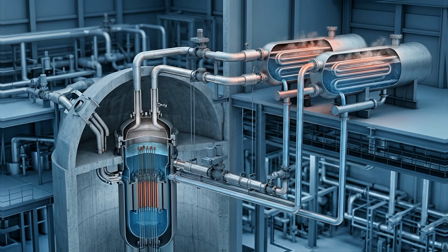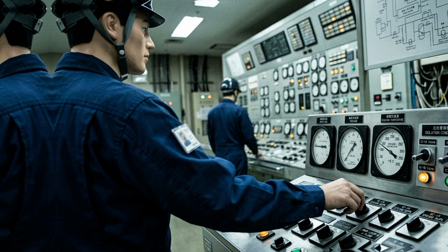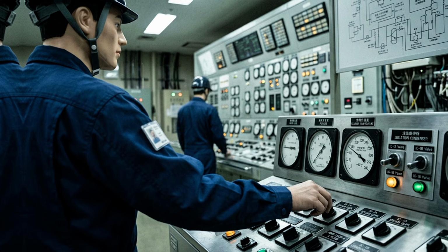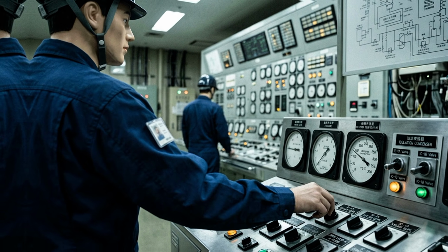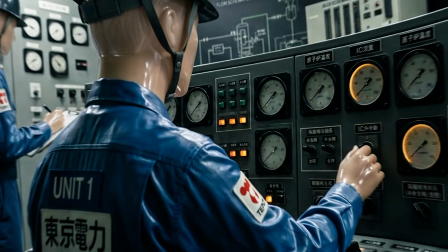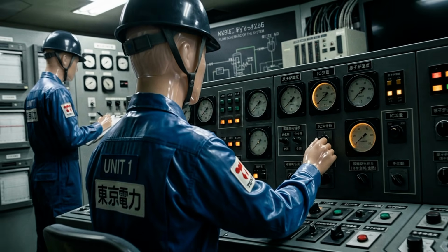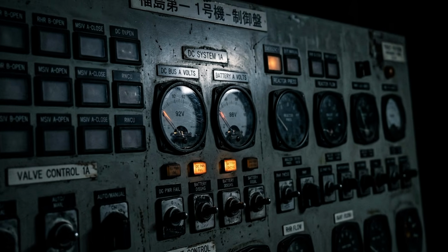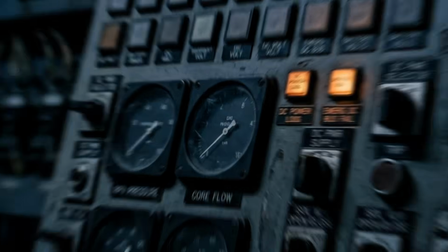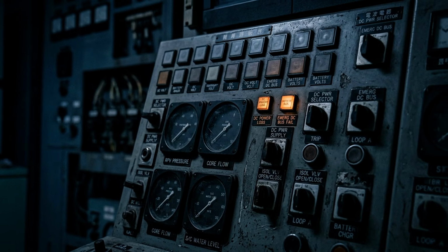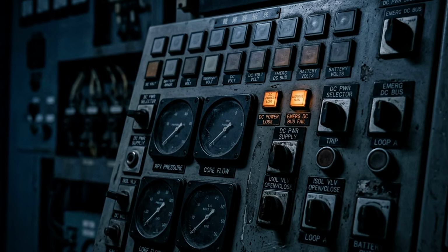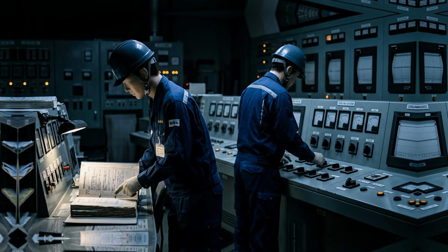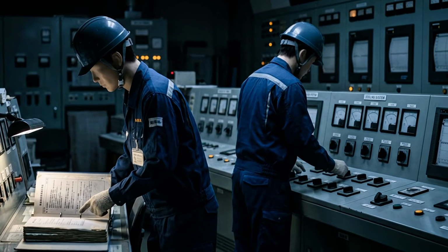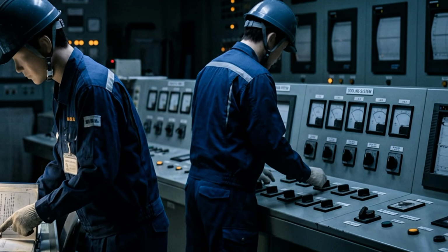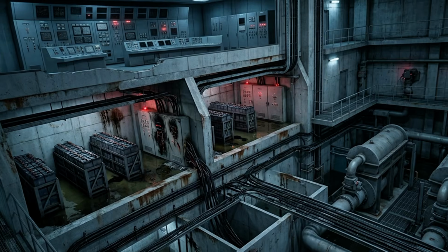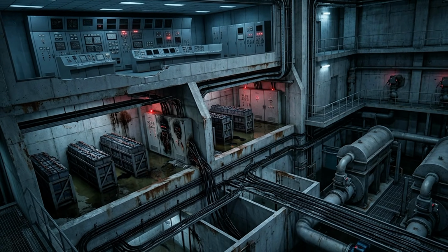After the earthquake, the system started automatically. Operators then stopped and restarted it because the reactor was cooling too quickly. Procedures required them to control the cooldown rate to avoid excessive thermal stress. Just before the tsunami, the isolation condenser had stopped. Then the flooding destroyed much of the electrical capability needed to monitor and control it. DC power was lost. Operators no longer had reliable indications of important valve positions. They attempted to restore cooling, but could not establish effective operation. The problem was not simply that the tsunami switched off a cooling system. It removed the power, information, and control capability needed to manage that system under deteriorating conditions.